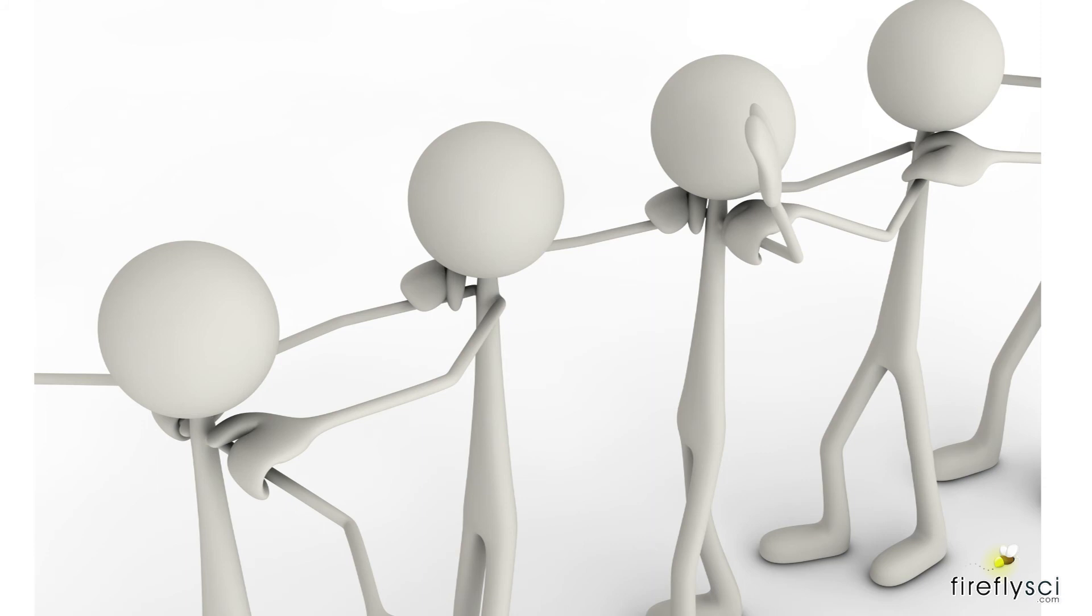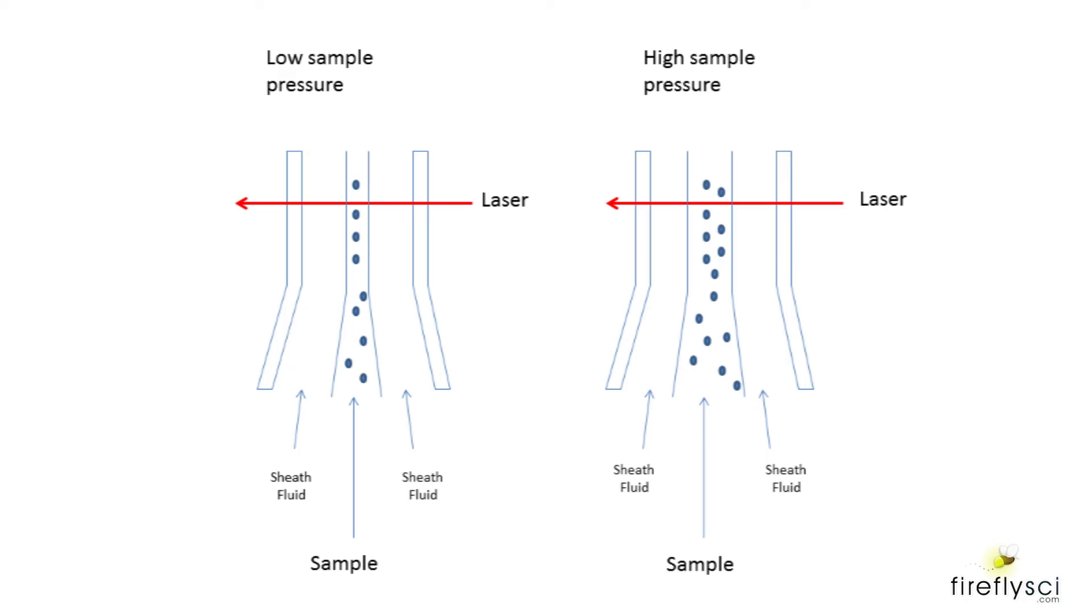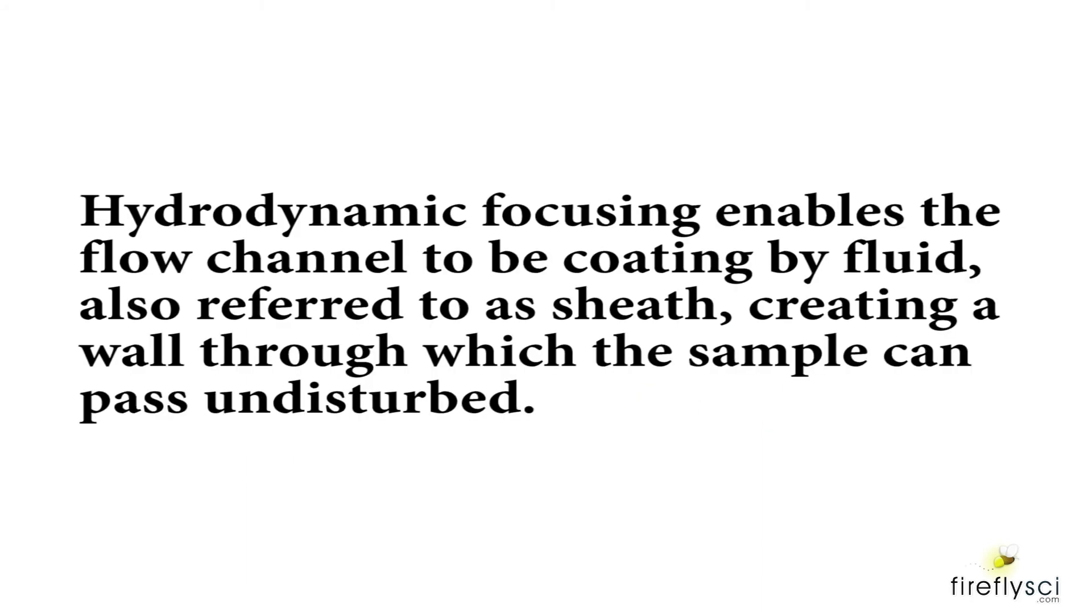The trick is to get all the cells to line up single-file like a conga line, so that they can be interrogated one at a time. This is where the principle of hydrodynamic focusing comes into play. Hydrodynamic focusing enables the flow channel to be coated by fluid, also referred to as sheath, creating a wall through which the sample can pass undisturbed.